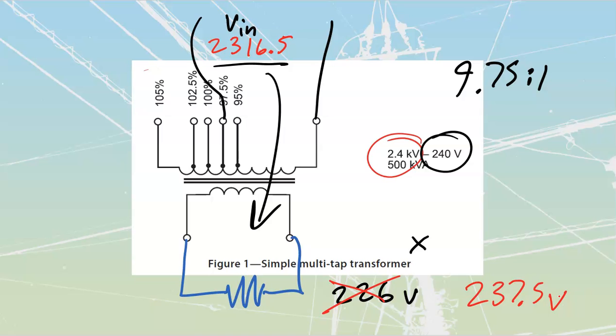What we're always going to be doing is figuring out what my incoming line value of voltage is. Once I know that, I then just need to find out what percent that is and move to the closest tap. Generally speaking, we go to the slightly higher tap so that our output voltage is slightly lower than rated. If I would have gone to this 95% tap, I would have ended up at about 244-ish volts. Nothing that's crazy critical, but nothing that's healthy either for our components.